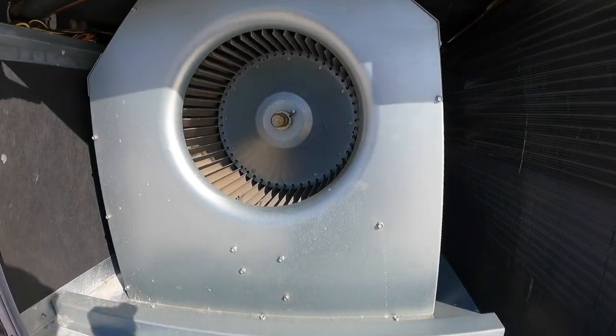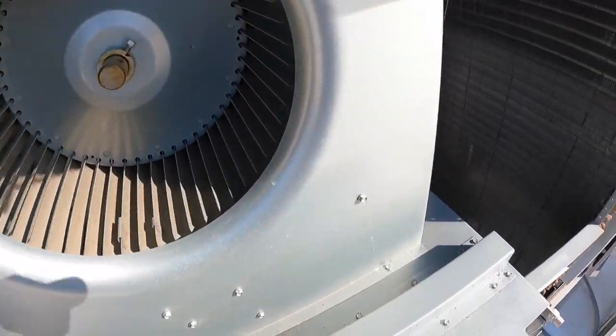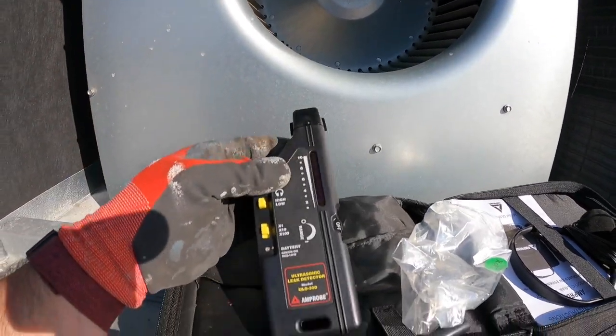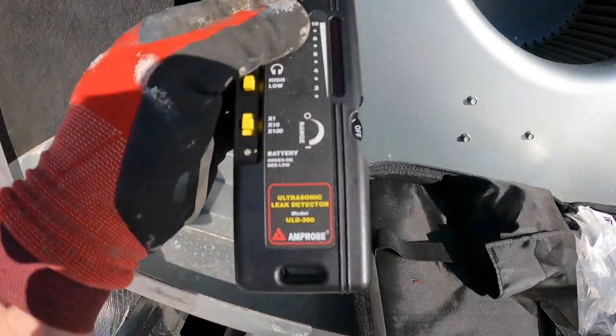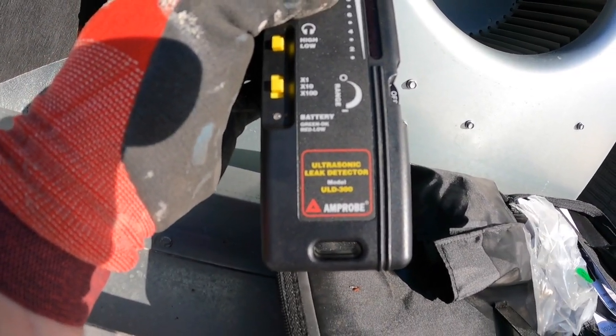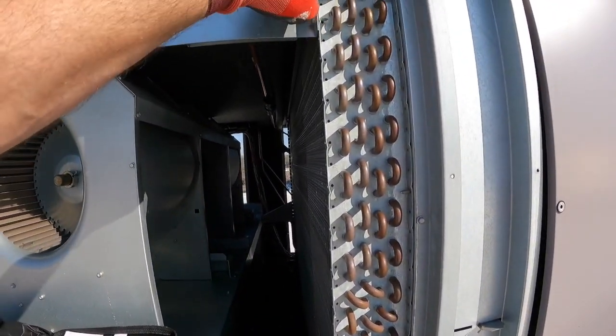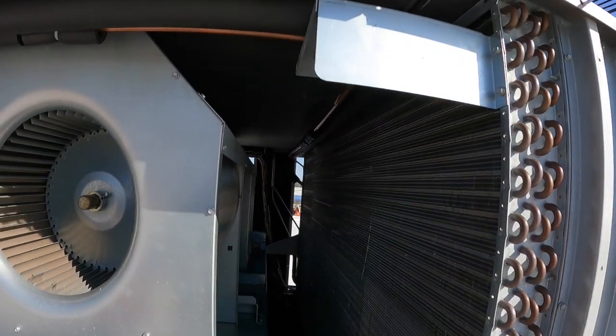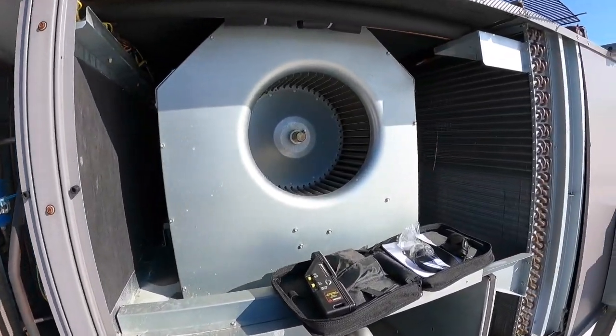We've got everything taken apart. I'm using an Amprobe ultrasonic leak detector — this is the model ULD 300. You can use whatever you like; I like being able to hear it. I'll put some headphones on and go over everything in this circuit — all these fins, both sides of the coil — and then go over the condenser coil for this circuit to see if I can identify where we're losing refrigerant.